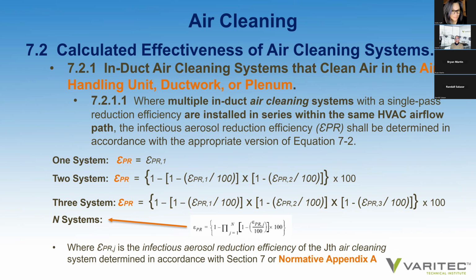If you have multiple air treatment technologies or air cleaning technologies in an air handler, filtration, UV lighting, ionization, maybe there's a combination of air handler plus in-room, depending on the risk of infection, occupancy, concentrations, etc. You can determine the infectious aerosol removal efficiency by either looking at one system, such as just using MERV 13 or MERV 14 filtration. You can look at two systems in an air handler, which would be your filtration system plus UVC lighting or ionization, or three systems perhaps. Anyway, you actually multiply each of the solutions in a system to determine the infectious aerosol reduction efficiency.